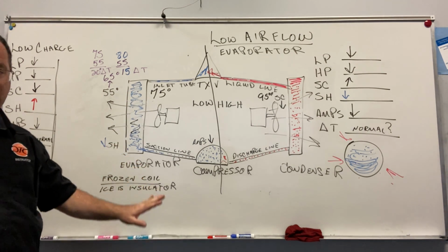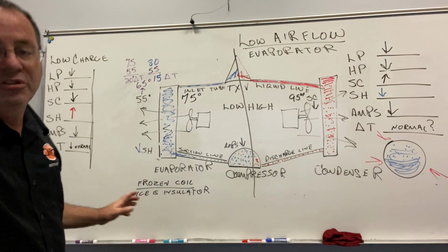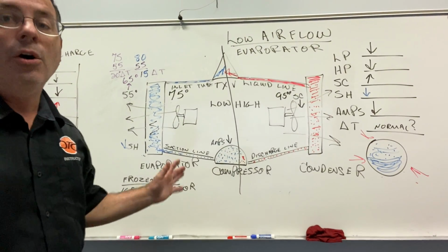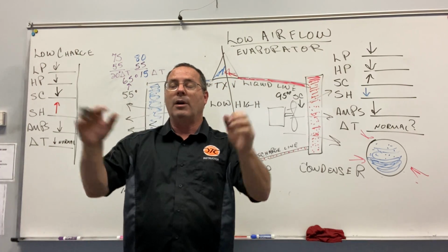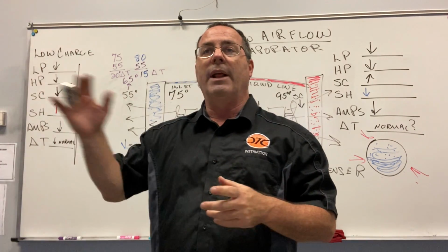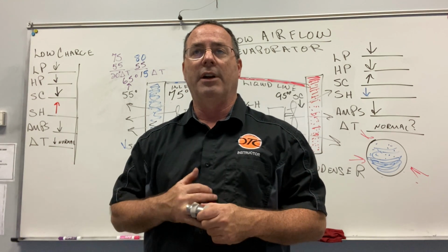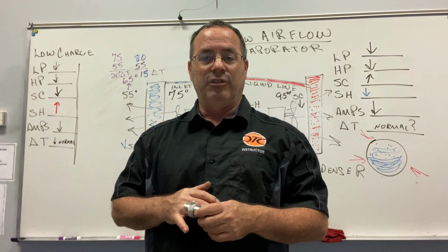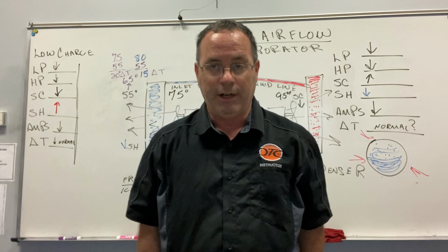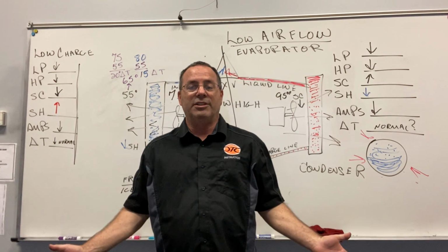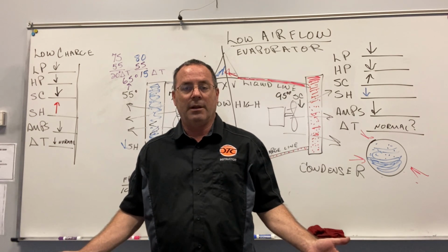Now I want you to think about this. Guys all the time go up to a unit and say, oh, it's frozen. It must be low charge. I had a guy once in here who went out and worked with somebody and they went to the unit, it was frozen, they thawed it out, put more Freon in the system. Came back 2 days later, it was frozen, put more Freon in the system. Came back 2 days later, put more Freon in the system. All they're doing is overcharging that unit. They're not fixing the problem.